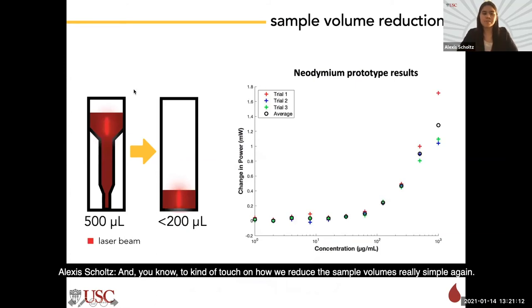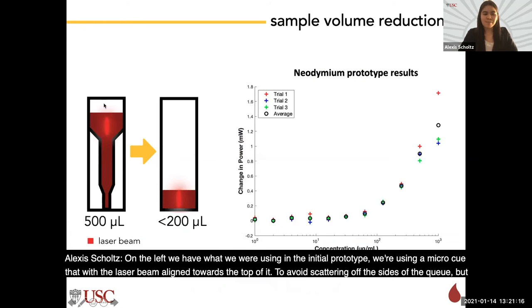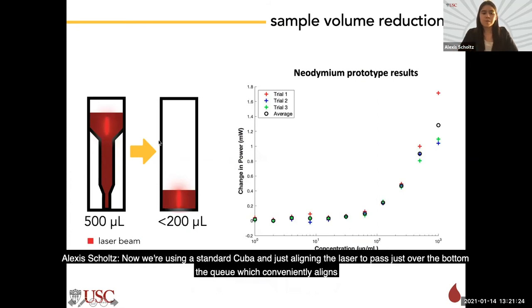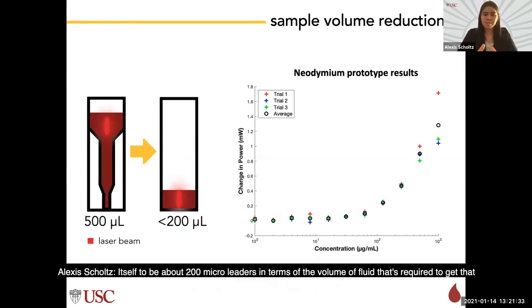To touch on how we reduced the sample volumes: on the left is what we used in the initial prototype, a micro cuvette with the laser beam aligned toward the top to avoid scattering off the sides. Now we use a standard cuvette and align the laser to pass just over the bottom, which conveniently corresponds to about 200 microliters of fluid required.